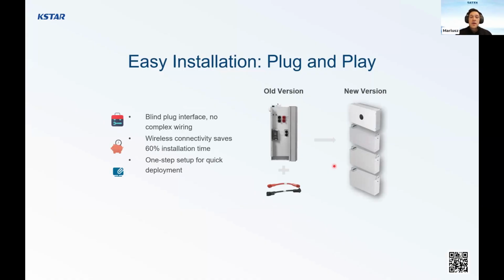Installation, plug and play. In the old versions, you had to buy the batteries, the inverter, and the cables, and then connect the cables to the inverters. And from my experience, sometimes it was problematic for the installers. With the new version, there is no such problem because we are stacking battery on battery and then the inverter. And on the next slide, I will show you what the installation process looks like.